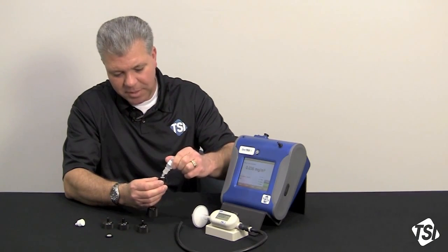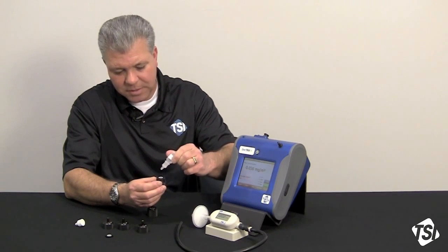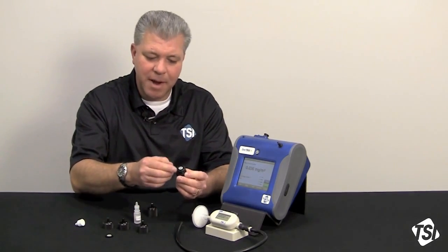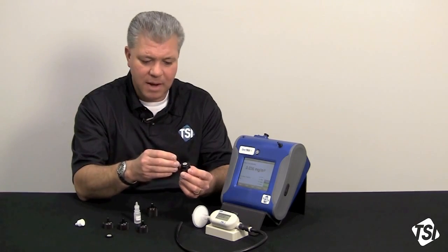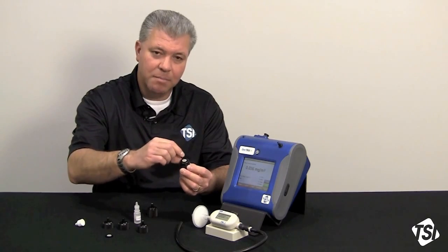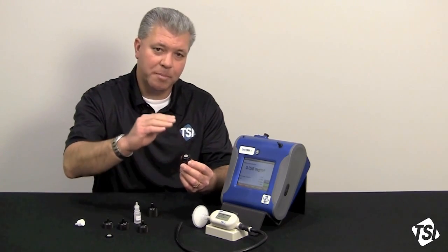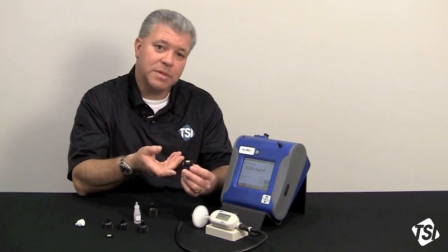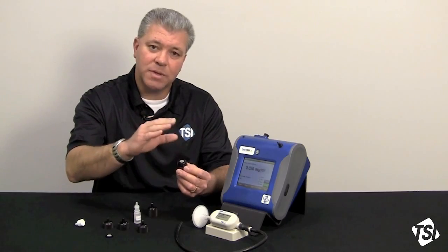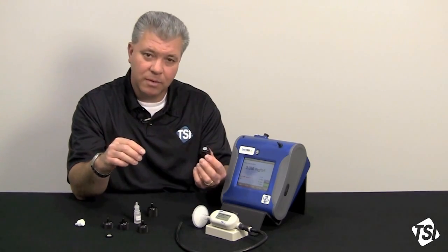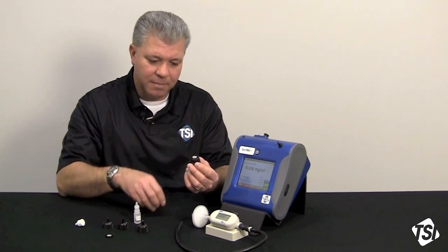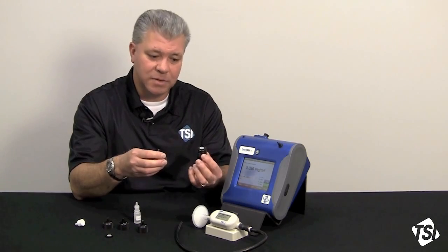So what we do in setting up an impactor is that we take 2 to 3 drops of impactor oil and we place that onto the impactor sintered head. There's 3 drops. What will happen is the impactor oil soaks into the sintered head, and as particles continue to impact on the plate, the particles wick up the oil and they continue to present a wet surface to particles that continue to hit. So that they don't bounce, they will continue to stick to the sintered plate, giving us a longer lifetime for the impactor to be used between maintenance intervals.